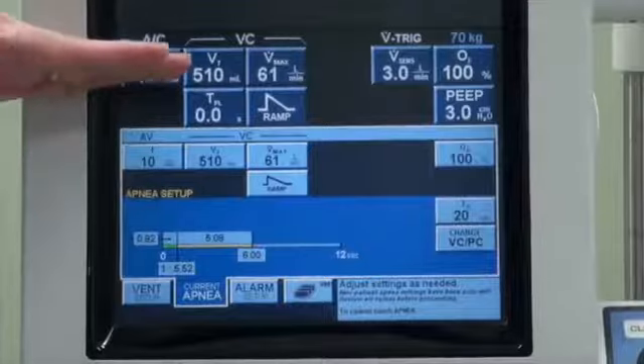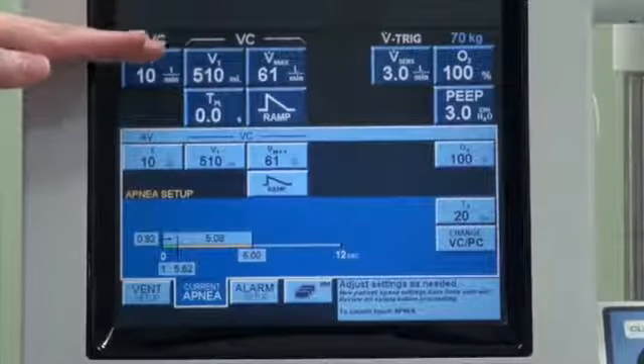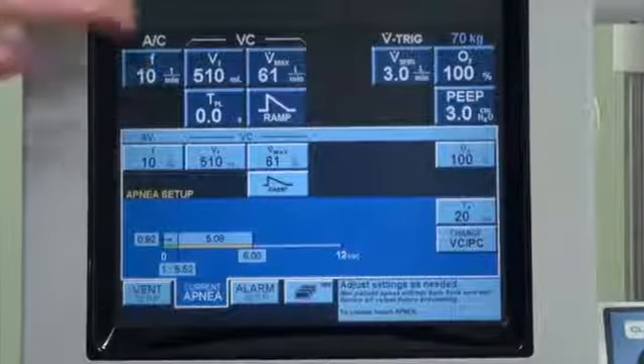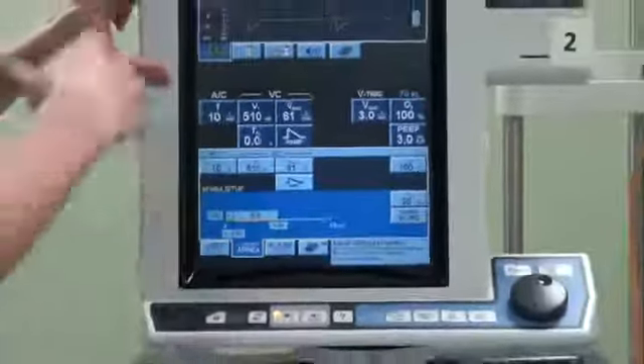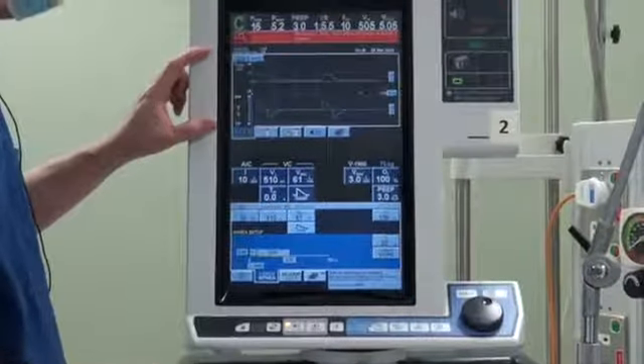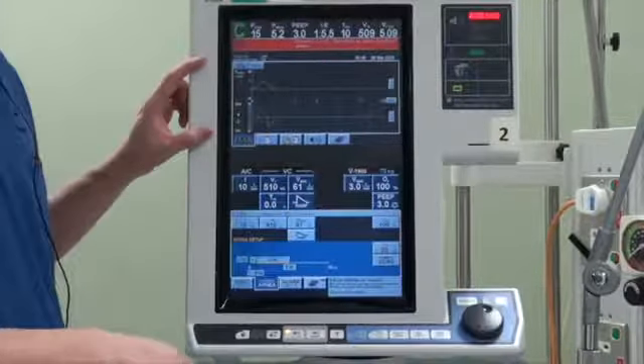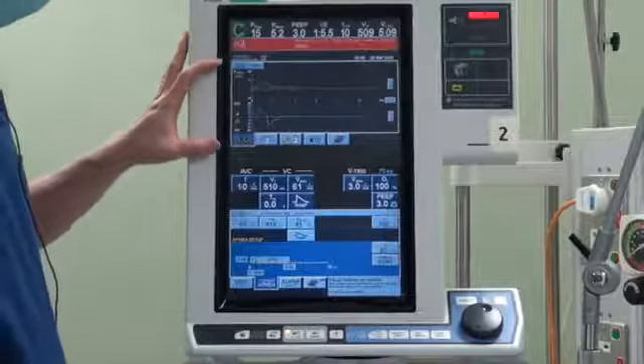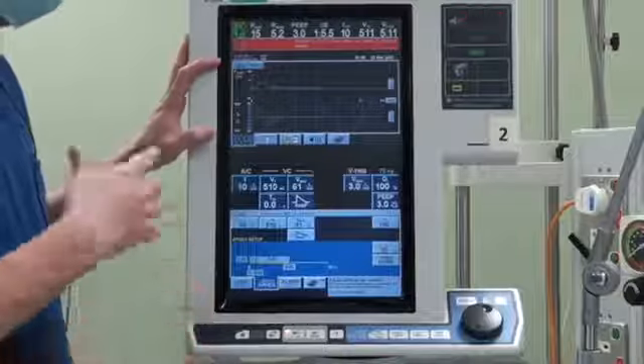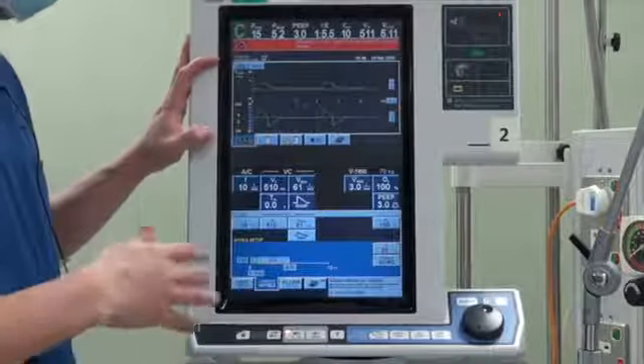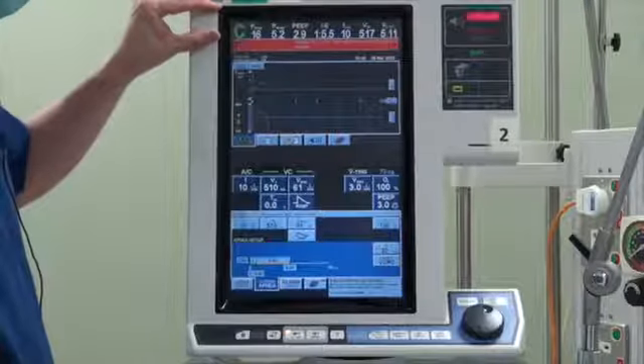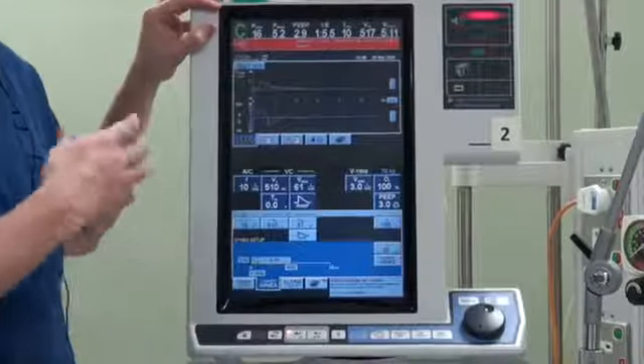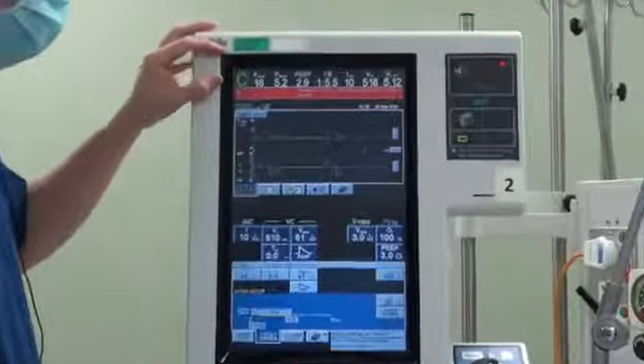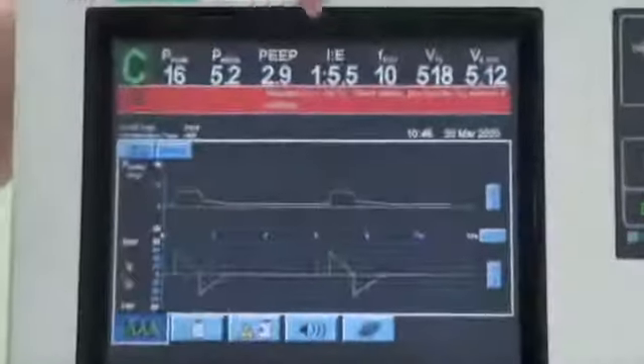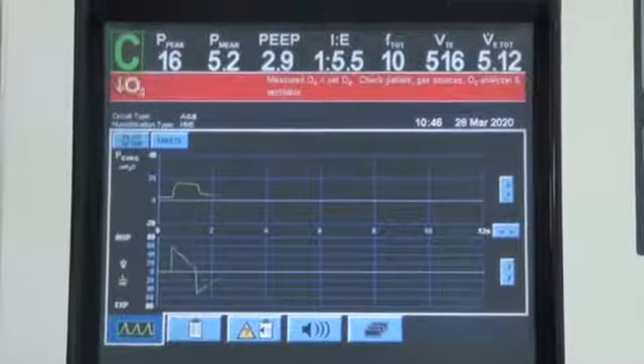Now that we are at the main screen that you'll be interacting with, you'll notice that this is a touch base with buttons at the bottom. The bottom half of the buttons are mechanical settings that you input. The central segments are the waveforms that help you to determine how well the patient is synchronizing with the ventilator. It's an important section to focus on because it helps you to determine whether there are any issues with how the mechanical ventilator is working with the patient. The top half is the parameters as recorded by the ventilator on the patient, so it will give you the reading that is measured from the patient.